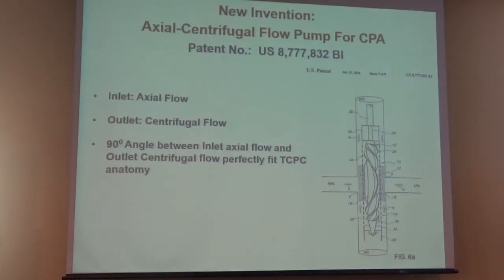If you go through the pump, in the cross section there is no place in failing Fontan circulation to accommodate any pump inside. It's very, very limited space. And then we are trying to do something like an axial-centrifugal flow pump to fit in the Fontan circulation inside the vena cava. Vena cava, especially in Fontan circulation patients, they have higher IVC pressure. Therefore, the vena cava is very, very big, which allows us to design the pump inside. This actually is very, very simple. The principle is very, very simple.